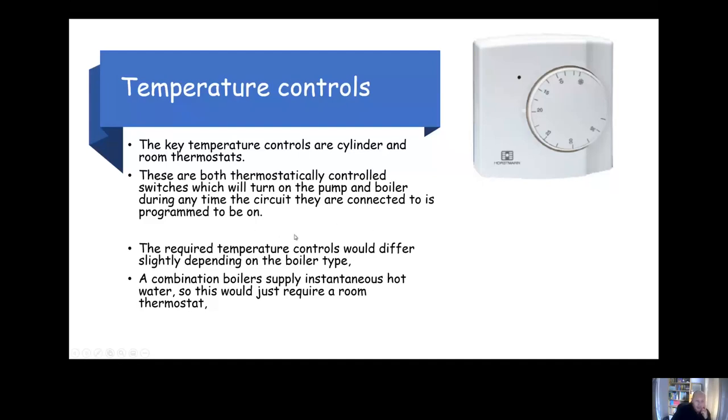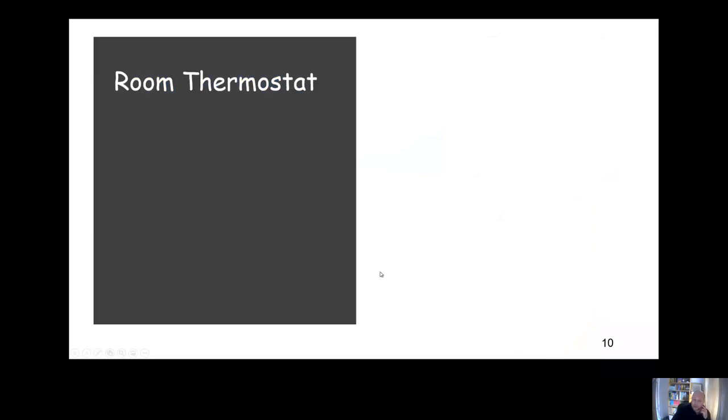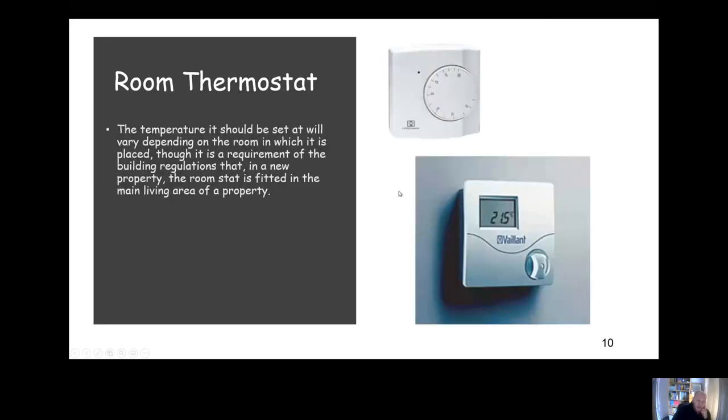So yeah, required temperature controls could differ depending on the boiler type. Obviously, a combination boiler wouldn't require a cylinder stat because it provides instantaneous hot water. If it does have a cylinder, make sure it's got a cylinder stat on the cylinder as well as the room stat in the living area.